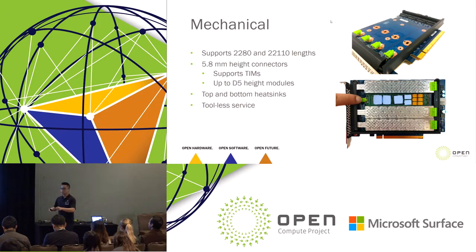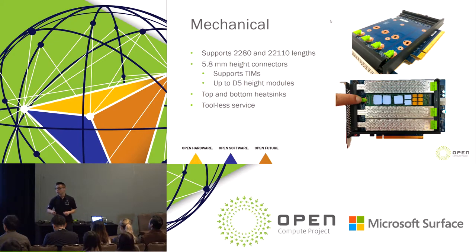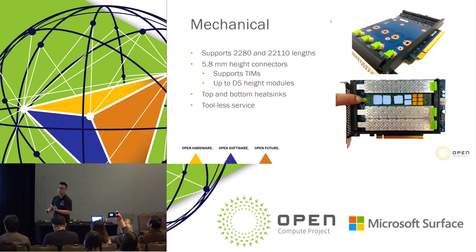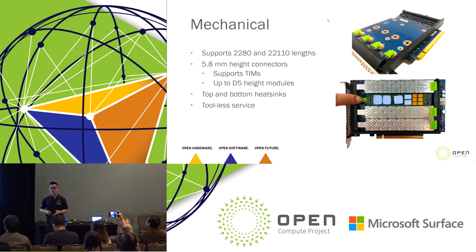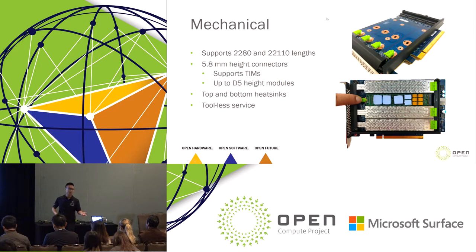In terms of connectors, we use a 5.8mm high connector. The reason is we want to support the D5 height module — the maximum thickness the M.2 specification provides. The M.2 spec specifies up to 4.2mm height, but we bumped it up to 5.8mm because we wanted to support thermal interface materials. We have top and bottom heat sinks — one top heat sink per M.2 — and true to Facebook design standards, tool-less service with all touchpoints outlined in green, so you can see how to replace an M.2.